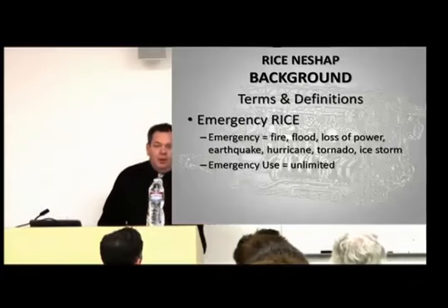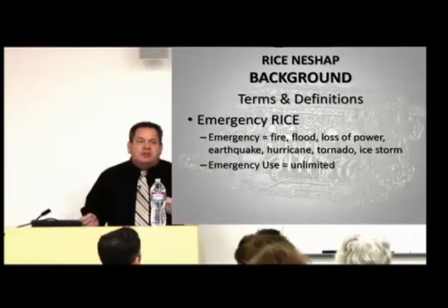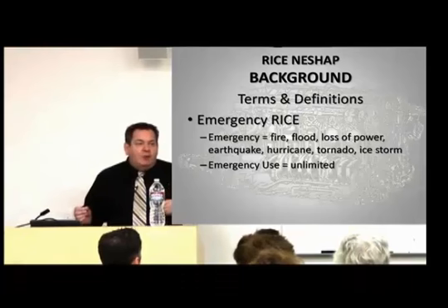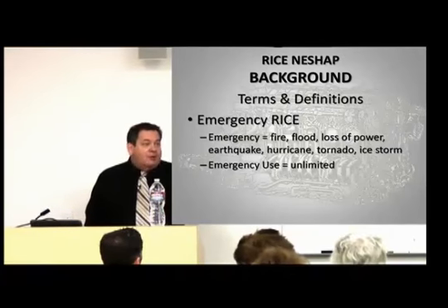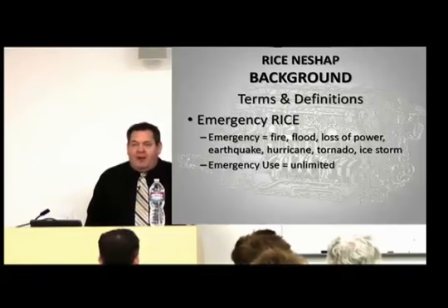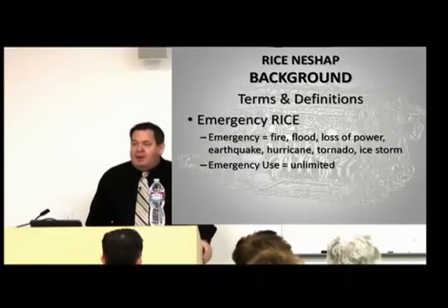Emergency RICE. The reason I'm defining this is that emergency engines don't have numeric emission limits. They have operational limits. They're limited to the amount of hours they run. And I really need to qualify this. They are not limited to the amount of hours they can run during an emergency.